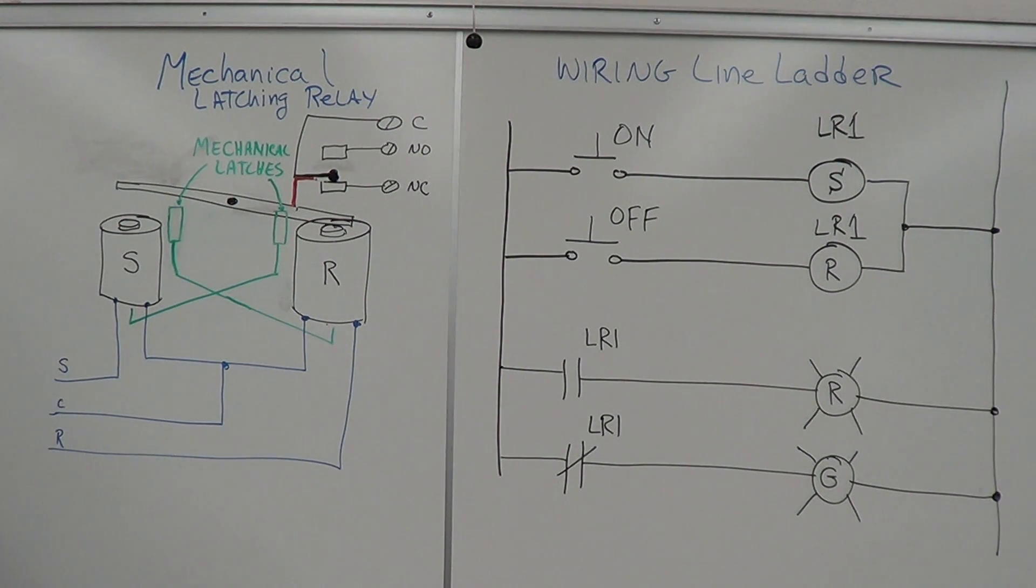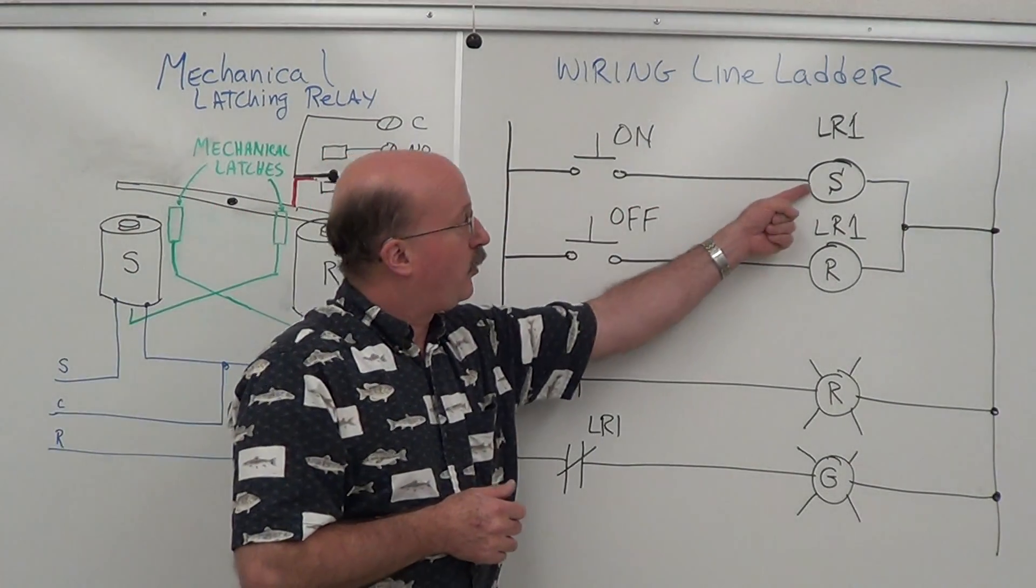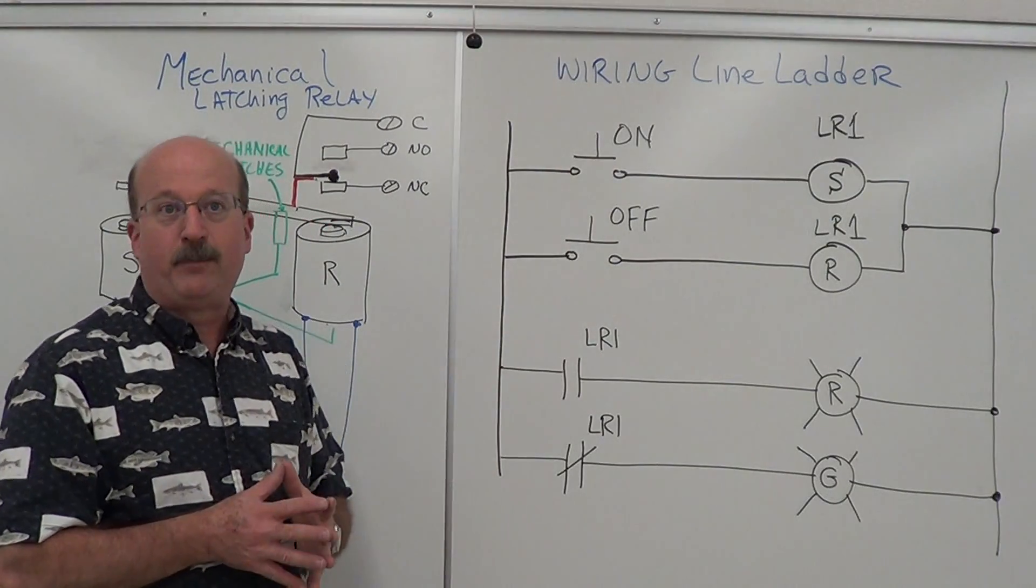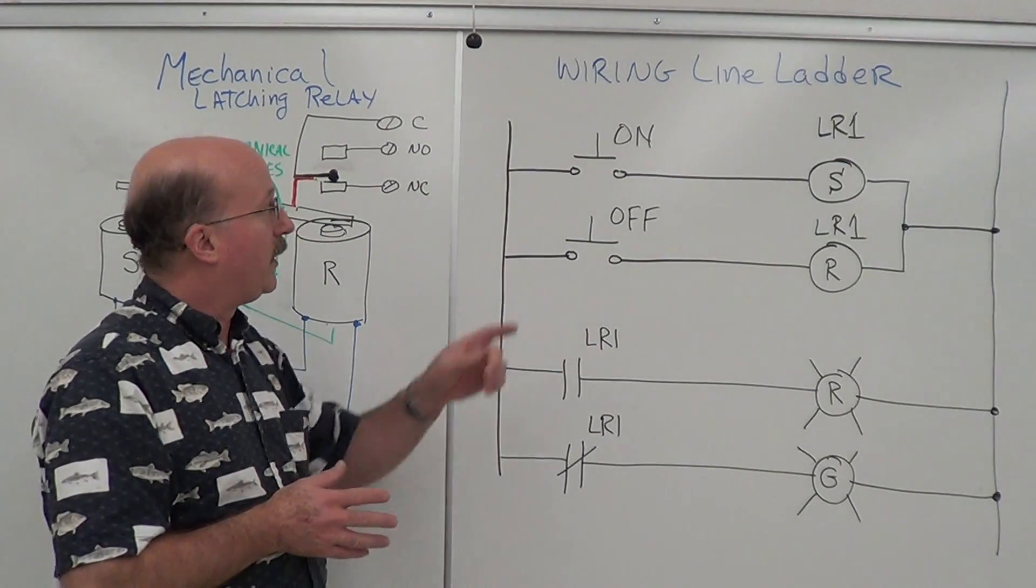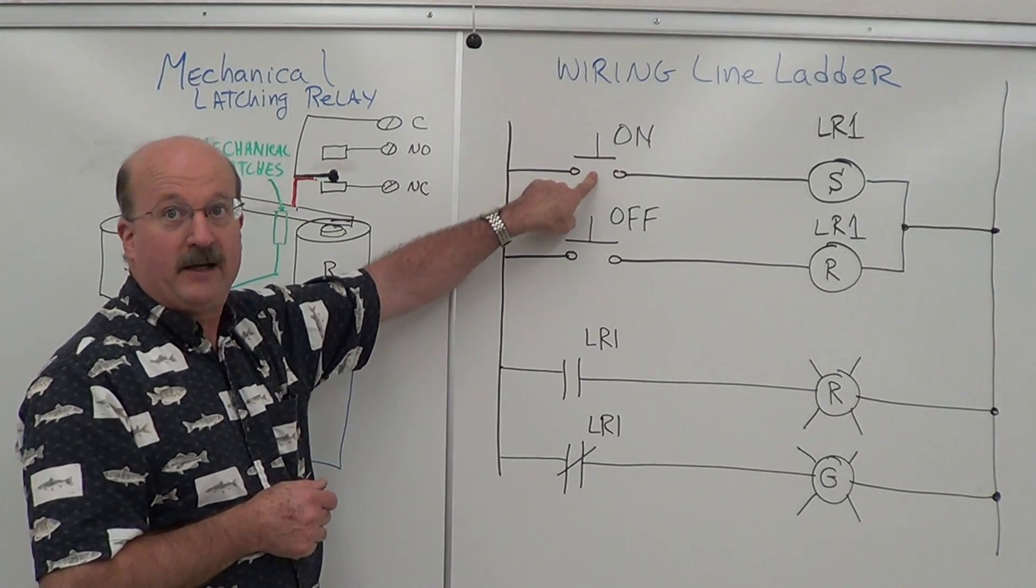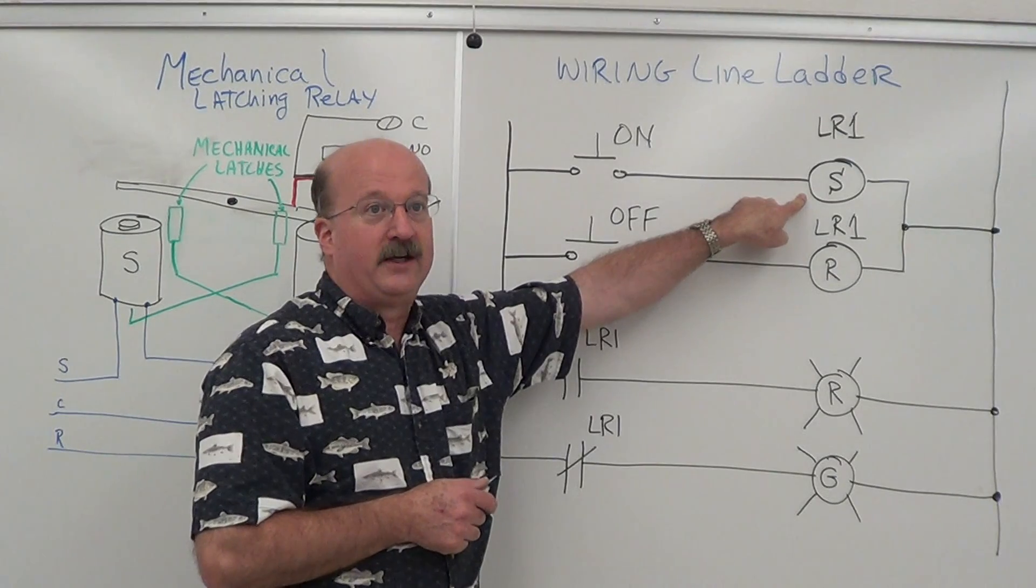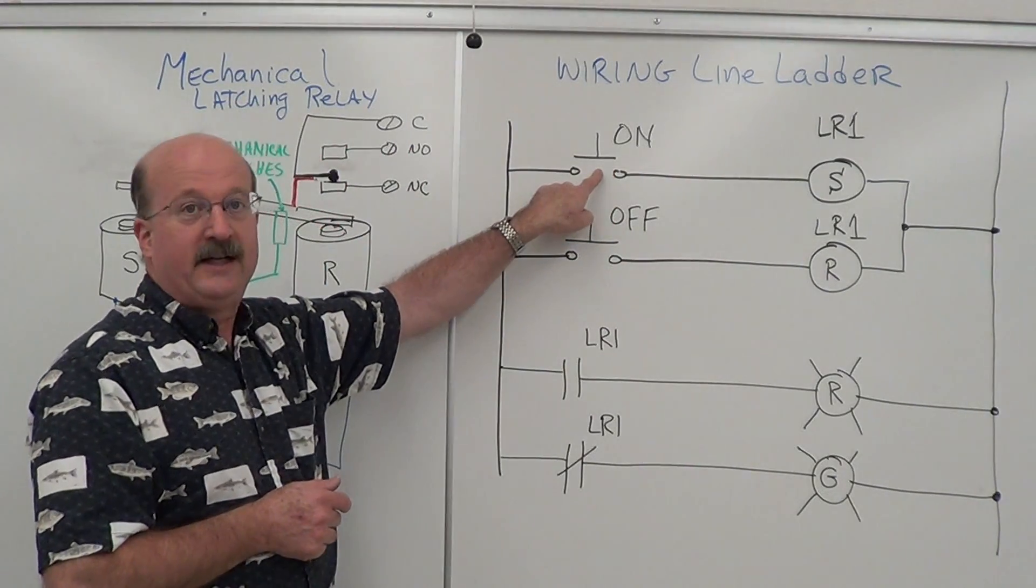Now if we look over here on the line ladder, we've got our two coils. They each have momentary push buttons energizing them. So if I want to turn the relay on, I push this button here, energize the coil, it'll switch and latch on. Then when I release the button, it will stay on.